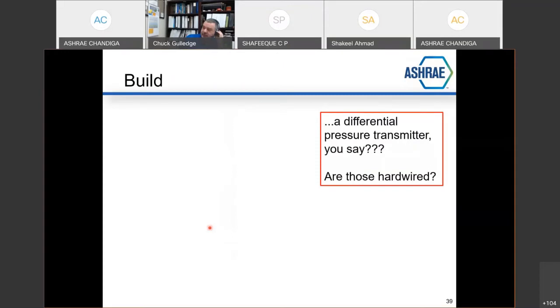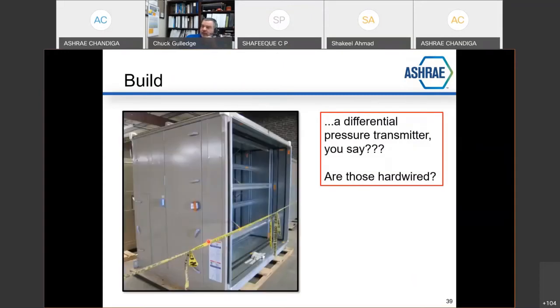Differential pressure transmitter, you say. Are those hardwired? So take a look at this. This is a filter section for a built-up air handler. You can see the frame configuration for where the filters slide in, and they slide in through this door. And for this client, this filter station was to have a combination gauge transmitter. Well, look at where they put the transmitter. They put it in the door. So the door has to open up, and there's no way to keep the probes and the wiring intact that are on the upstream and downstream side of the filter. This should have been placed here in a fixed surface and the tubing put upstream and downstream of the filters. But no, somebody put it in the moving door.